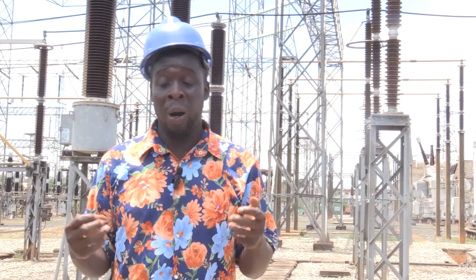Engineer Dr. Ifeanyi, manager and TCN substation operator in charge of the New Haven Transmission Substation, describes the facility: one 330 kV station comprised of 4 by 150 MVA transformers, stepping down 330/132 kV, with a capacity of carrying 600 megawatts.